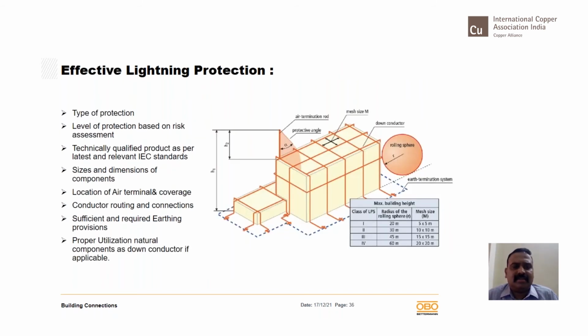Right. How do we achieve an effective lightning protection system? What are all the factors you need to look at when you design lightning protection effectively? First and foremost is the type of protection, whether you are going for the angle of protection method, the mesh method, or the rolling sphere method. This is to be determined depending on the nature of the building. Then, what level of protection and what kind of risk assessment is to be done. Thirdly, technically qualified products as per the latest and relevant IEC standards. Many lightning protection products are being rated as per IEC 62561 to ensure that certain tests are mandatory for the components to be used.